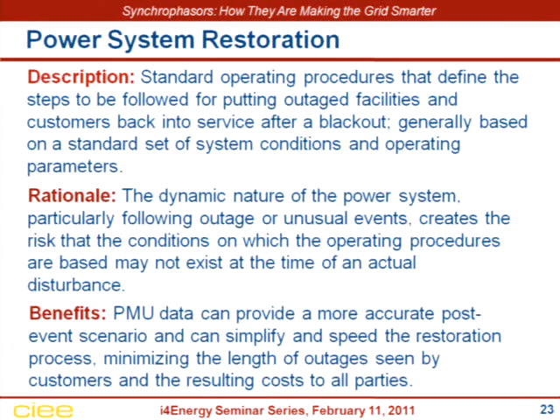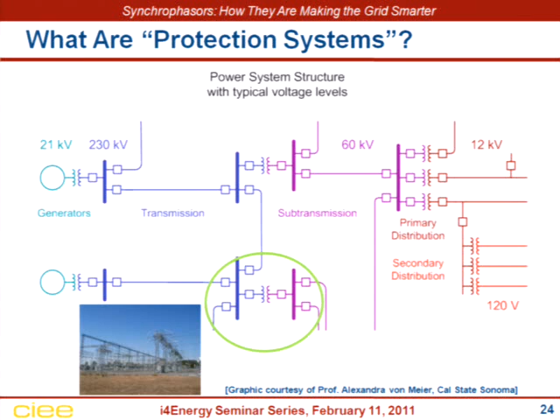I'm going to talk about protection systems a bit, because this relates to the DOE project I mentioned on adaptive protection. Protection basically starts with circuit breakers - these little boxes here. A circuit breaker will protect a transformer, a line, or a generator depending on what you're trying to protect. With a generator, if it starts to overspeed, underspeed, or over-torque too much, you want to trip it off. If a transformer gets overloaded, you want to trip it off too. These circuit breakers are designed to be automatic switches that open up and separate the equipment from the system so it doesn't get damaged, or so the system doesn't get damaged.